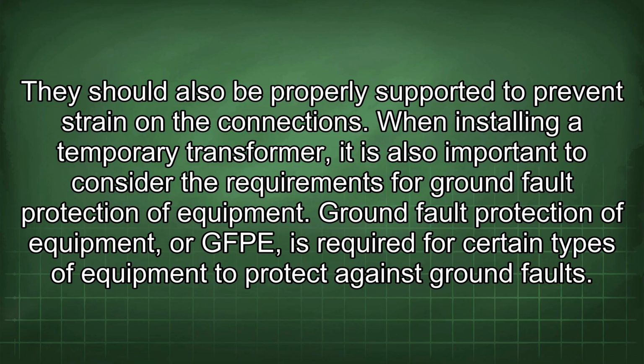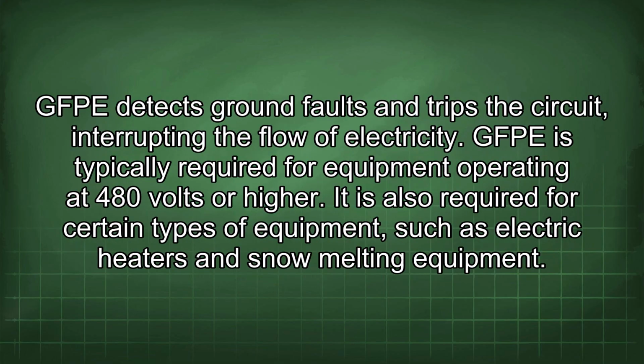When installing a temporary transformer, it is also important to consider the requirements for ground fault protection of equipment. Ground fault protection of equipment, or GFP, is required for certain types of equipment to protect against ground faults. GFP detects ground faults and trips the circuit, interrupting the flow of electricity. GFP is typically required for equipment operating at 480 volts or higher. It is also required for certain types of equipment, such as electric heaters and snow melting equipment.